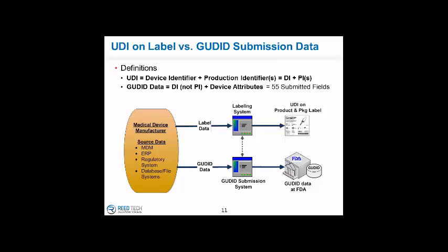As you're considering your UDI methodology and system, you'll need to consider both the labeling system: how do you mark the UDI onto the product, where do the values come from, how are they maintained, who manages them, how are they allocated to the product, and what particular issuing agency you have, GS1, or maybe HIBCC, or ICCBBA. There are actually 3 that you're able to select, and then how do you get it on the product?